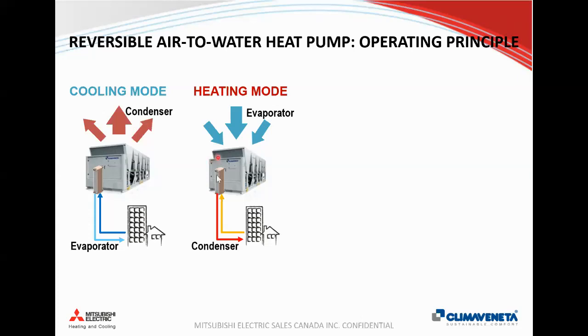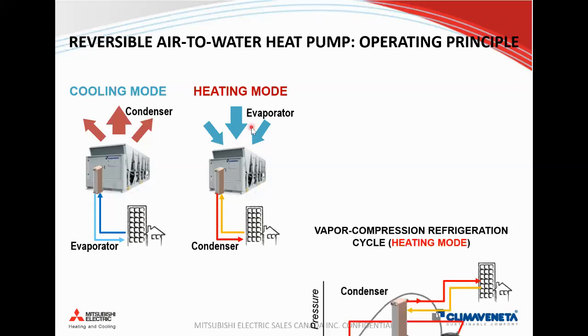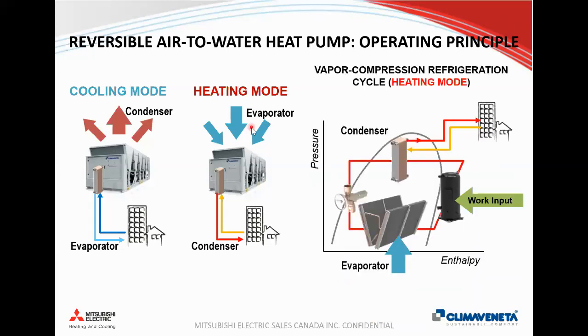So essentially in heat pump mode, we're just swapping which heat exchangers provide which function. The indoor heat exchanger connected to the building in wintertime is now acting as a condenser, so we're rejecting heat. And we're doing that by absorbing heat from the integrated coil in the machine, which is acting as an evaporator. So it's just the basic vapor compression refrigeration cycle. By putting work into a compressor, we're moving heat from one location to another to provide hot water to our building in heating mode.